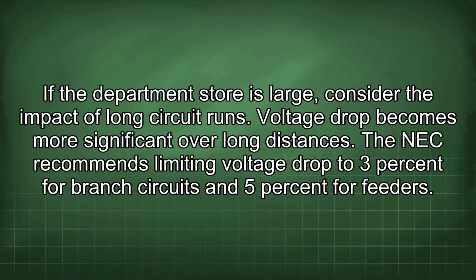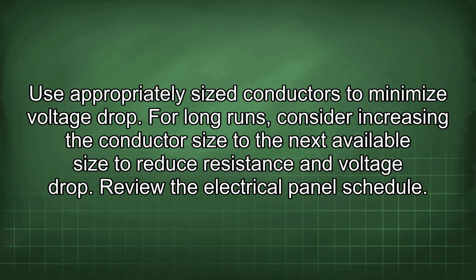If the department store is large, consider the impact of long circuit runs. Voltage drop becomes more significant over long distances. The NEC recommends limiting voltage drop to 3% for branch circuits and 5% for feeders. Use appropriately sized conductors to minimize voltage drop. For long runs, consider increasing the conductor size to the next available size to reduce resistance and voltage drop.